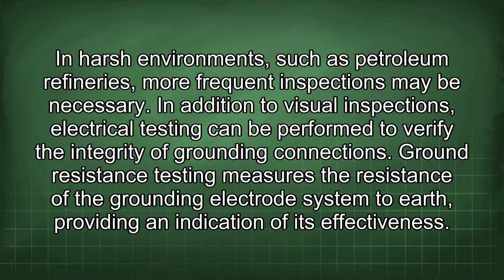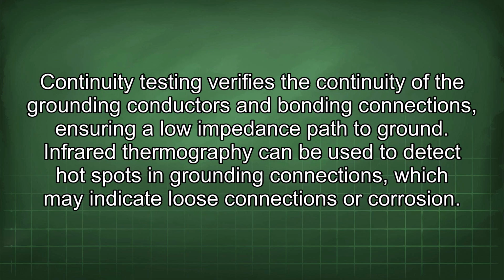In addition to visual inspections, electrical testing can be performed to verify the integrity of grounding connections. Ground resistance testing measures the resistance of the grounding electrode system to earth, providing an indication of its effectiveness. Continuity testing verifies the continuity of the grounding conductors and bonding connections, ensuring a low impedance path to ground. Infrared thermography can be used to detect hot spots in grounding connections, which may indicate loose connections or corrosion.